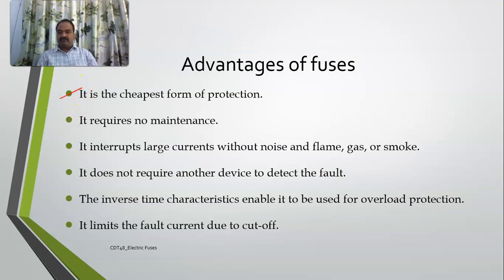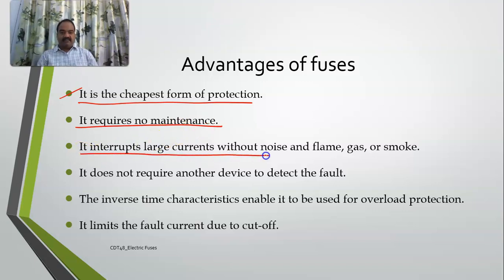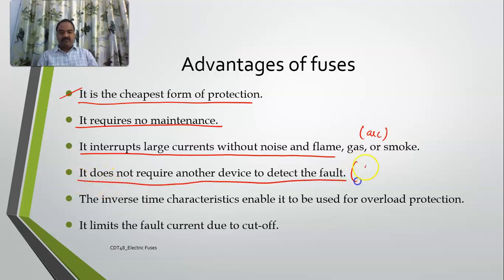The advantages of a fuse: it is the cheapest form of protection available. It requires no maintenance — it just blows off when there is a high current and you replace it. It interrupts large currents without any noise, flame, gas, or smoke, though an arc may appear sometimes. It does not require any additional device to detect faults — unlike protection schemes that use relays, no auxiliary relay is needed.